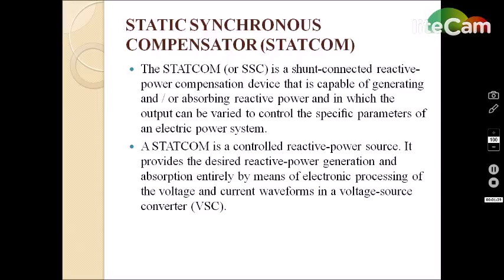So STATCOM is a shunt connected reactive power compensation device capable of generating and absorbing reactive power, where the output can be varied to control specific parameters of an electric system. Here, the reactive power generation and absorption are done entirely by electronic processing of the voltage and current waveforms in a voltage source converter.